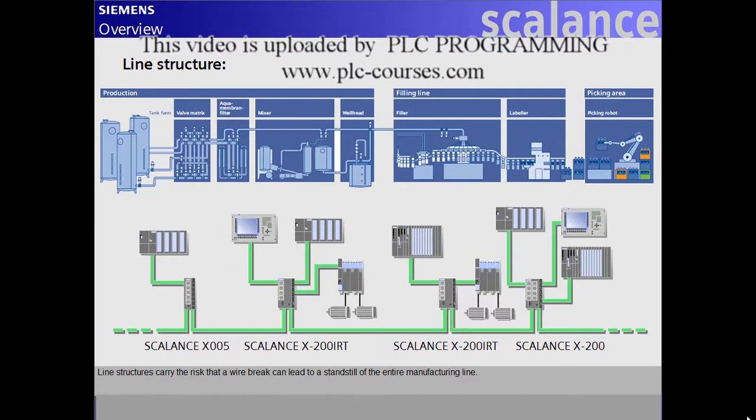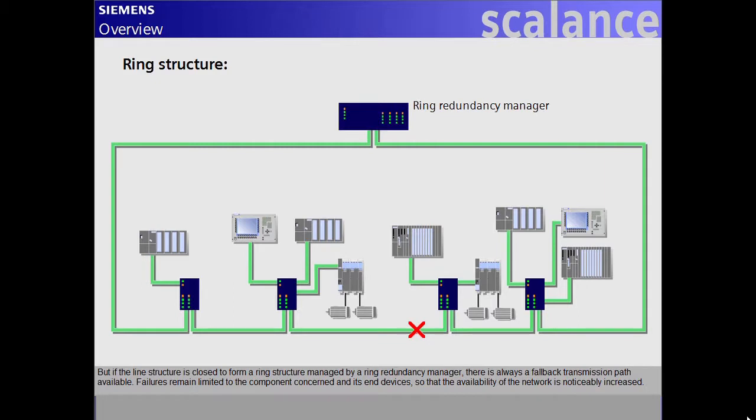Line structures carry the risk that a wire break can lead to a standstill of the entire manufacturing line. But if the line structure is closed to form a ring structure managed by a ring redundancy manager, there is always a fallback transmission path available. Failures remain limited to the component concerned and its end devices, so that the availability of the network is noticeably increased.